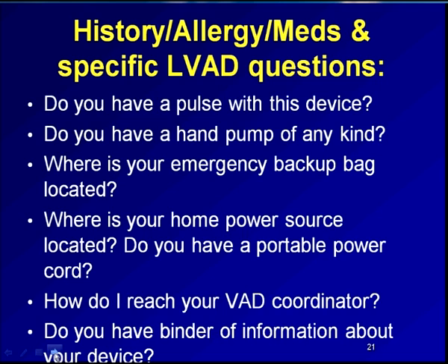In today's times, almost all these devices have phone numbers either on the controller or on the tag associated with an emergency bag or any kind of power source. That tells you exactly how to contact their VAD coordinator who manages these patients, if these patients don't already have them on the phone when you arrive. That VAD coordinator is going to help you through this emergency.